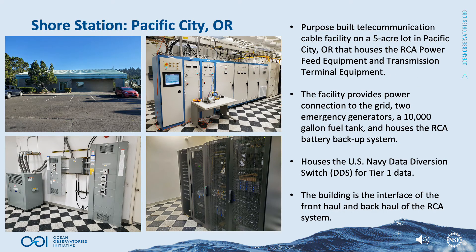The RCA shore station is a purpose-built telecommunication cable facility on a five-acre lot in Pacific City, Oregon, that houses the RCA power feed equipment and transmission terminal equipment. The facility provides power connection to the grid, two emergency generators, a 10,000-gallon fuel tank, and houses the RCA battery backup system. It also houses the U.S. Navy data diversion switch for Tier 1 data, and serves as the interface of the front haul and back haul of the RCA system.